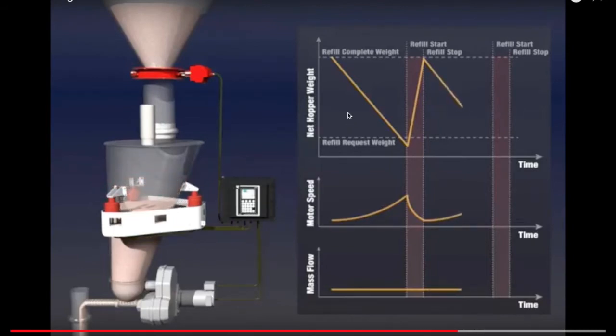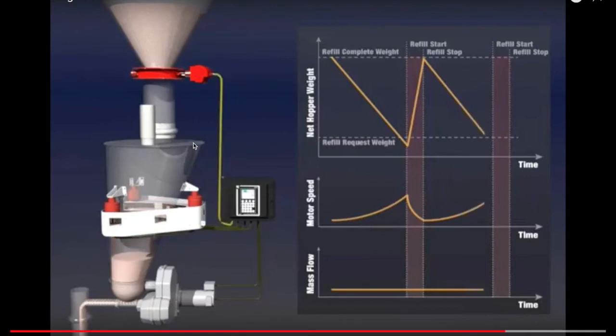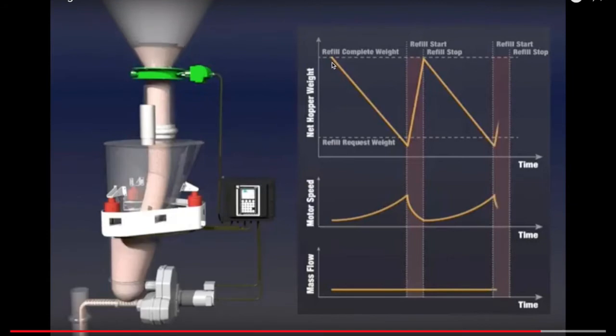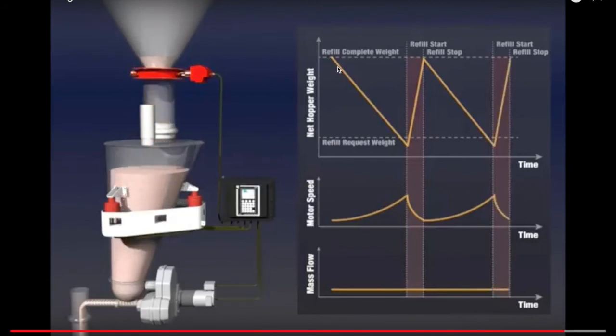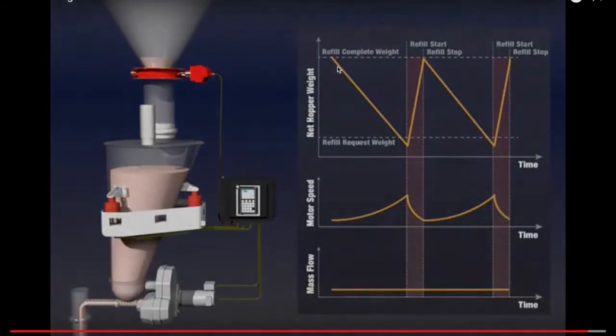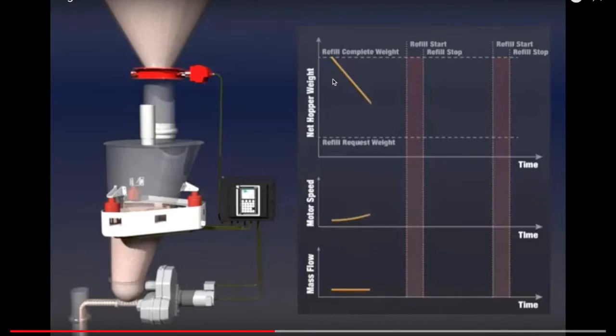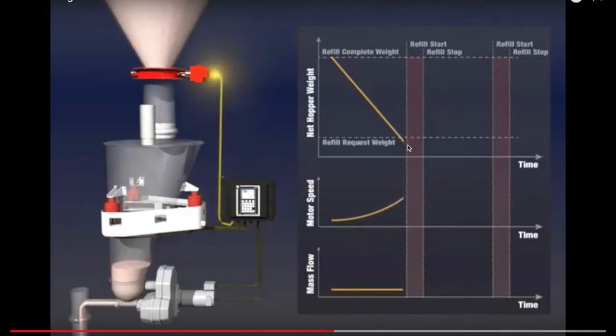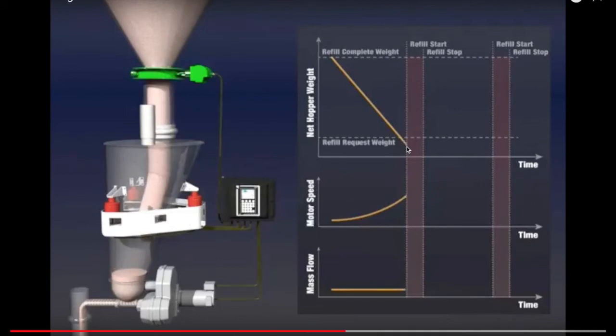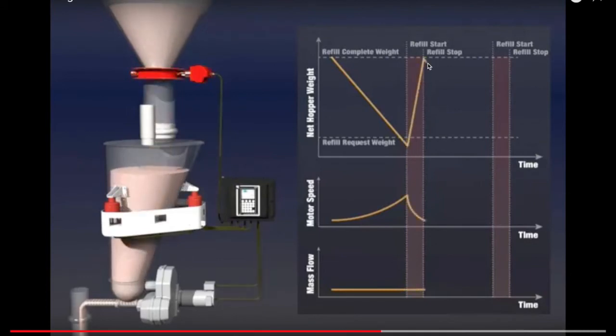So looking over on the right, there is the net hopper weight. So the hopper is what I've been calling the surge tank. And over time, given what is presumably a constant flow rate, the hopper, or the surge tank, is constantly losing weight. It gets to a refill point, and of course the weight that is measured in the hopper increases, and then it starts feeding again and coming down.